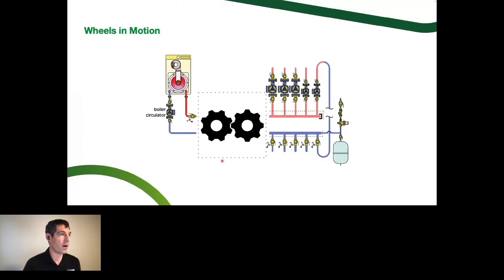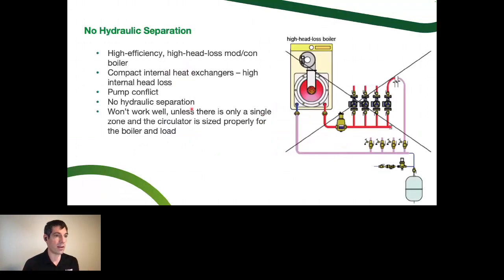Inside of this box right here, we have to do something to keep these two gears from fighting, to keep these gears from grinding. What that means in a hydronic system is that if we have gears in conflict like this spinning at different speeds, we're going to influence flow on one side of the equation or the other. So we may be pushing way more flow than we need through the boiler heat exchanger, or we may be way less than we need in some scenarios. And we don't want that. We don't want these two different things to fight each other. We've got to put in some sort of device in the center. So broadly speaking, what we're talking about is primary secondary piping.